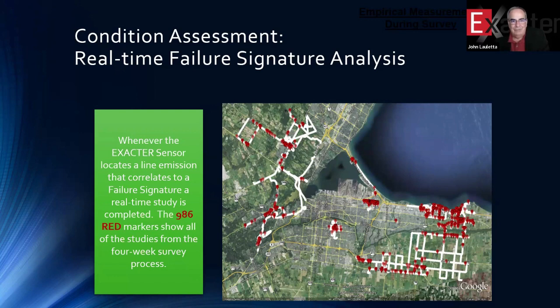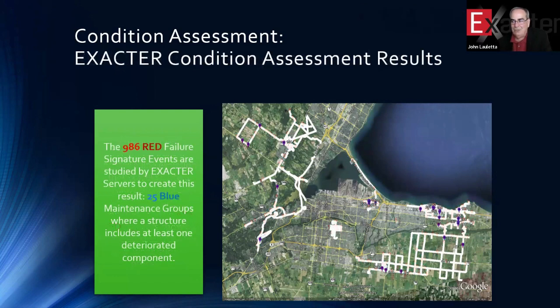It's more of an echo of a partial discharge event somewhere else. So our secondary analysis eliminates those partial discharge phantoms and partial discharge transients, and leaves us just with, out of that 1,000 readings, 25 places on this grid, probably about 100 miles or so, that have an insulator at these points or more, maybe more than one insulator or device that should be replaced to eliminate the problem.